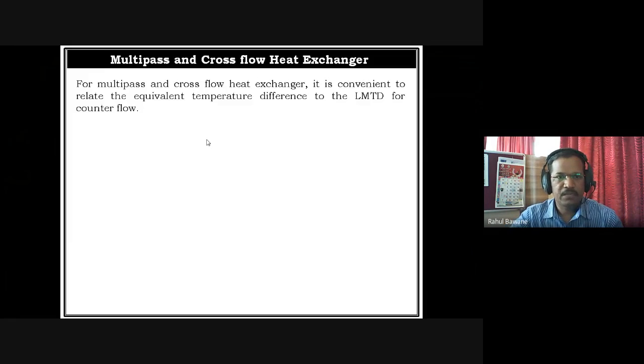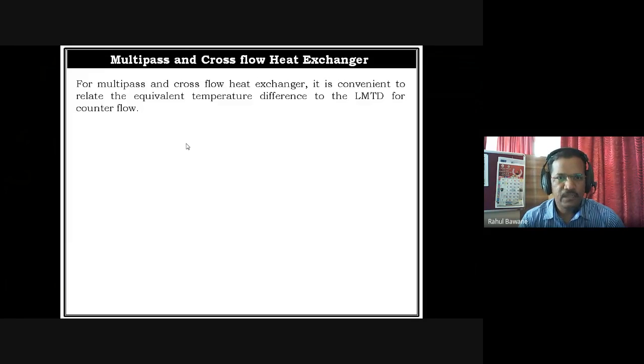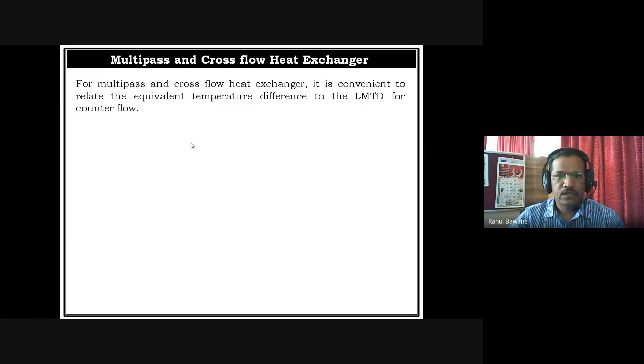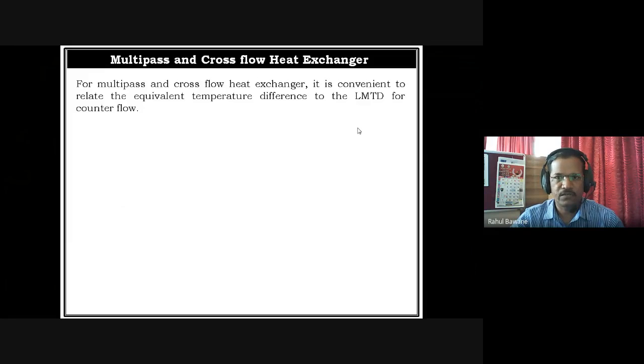Multi-pass might be two passes, four passes, six, or eight — in multiples of two. There is a possibility to have shell fluid with multi-pass or tube fluid with multi-pass. The second type is cross flow, where two fluids move in a direction 90 degrees to each other. In cross flow, there is a possibility of having a mixed or unmixed kind of cross flow heat exchanger.